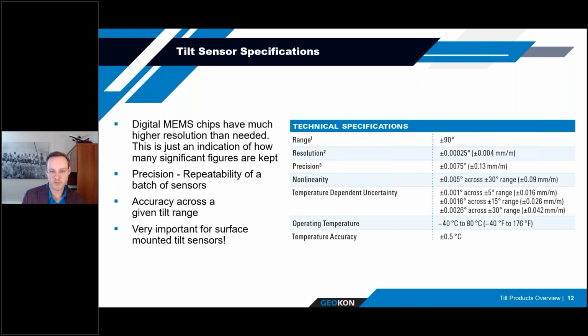The next item is resolution, and you can see that this is a very small number at plus or minus 0.004 millimeters per meter. With the modern digital MEMS chips, the resolution is typically much higher than is really required, and is actually just a function of the number of significant figures that are kept throughout the data processing phase of taking a reading from the sensor. So, you know, this is really a meaningless number when you're looking at quality of data for tilt products, and you really just need to see that that number is better than the precision value.